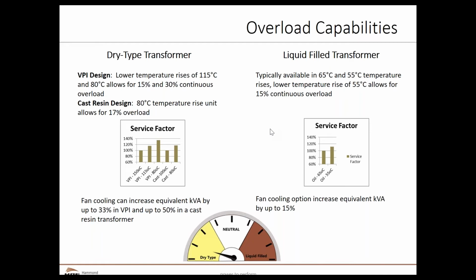So in some cases, this is actually a valuable tool to understand, because in some cases we do see people greatly oversizing the liquid filled transformer because of either the environmental temperatures or potential for brief overloads. And as a result, the kVA differences between liquid and dry type may be calculated differently.